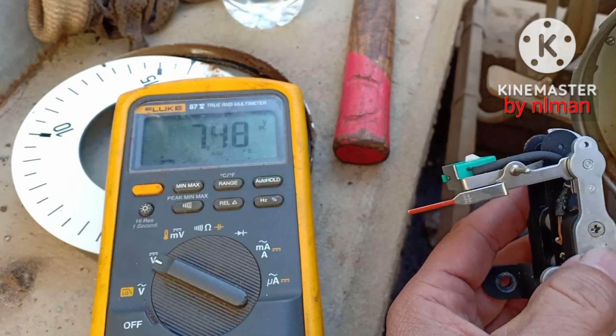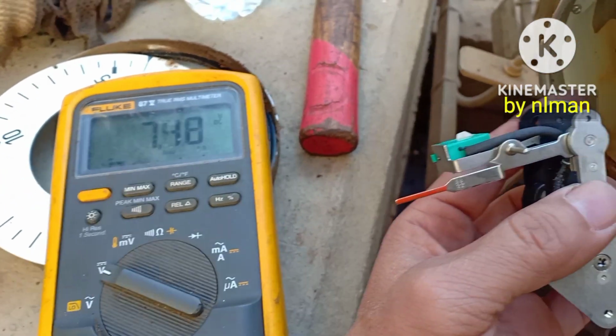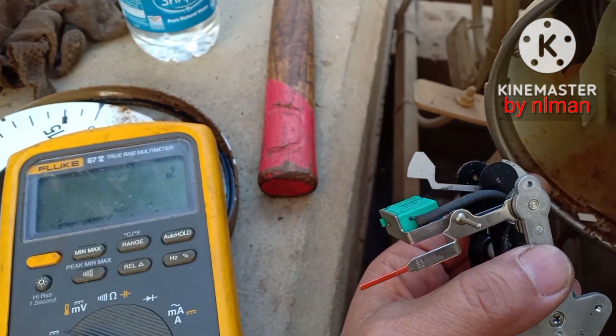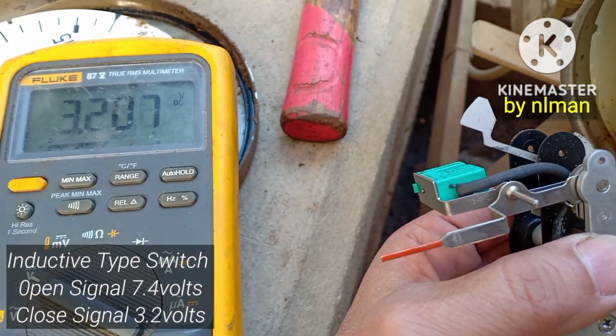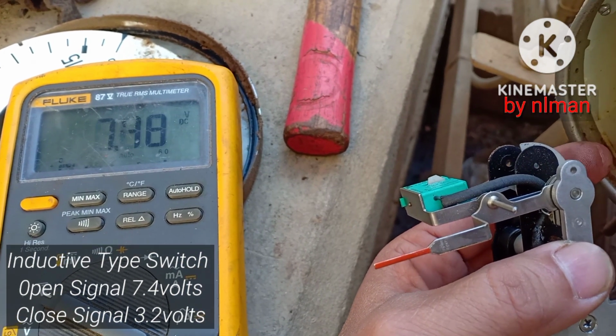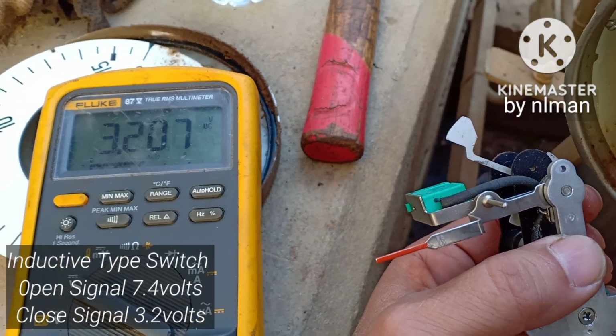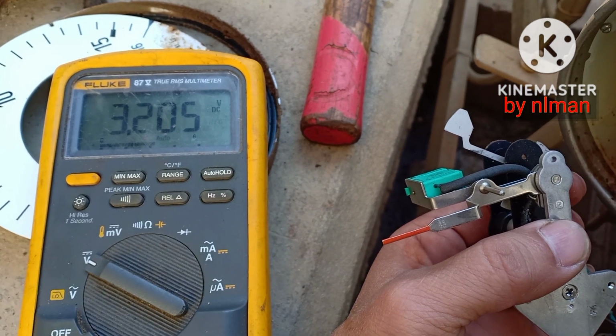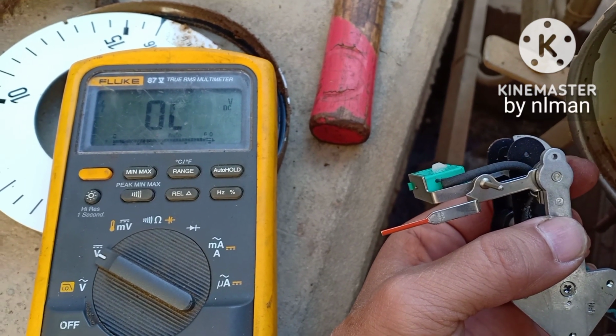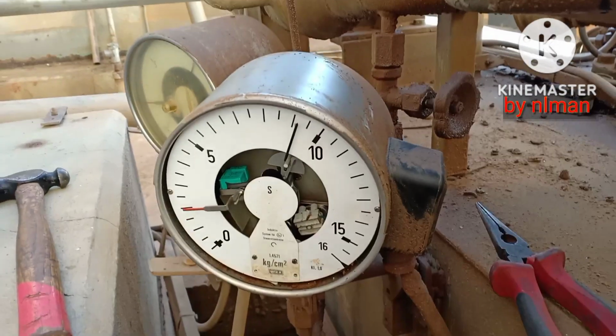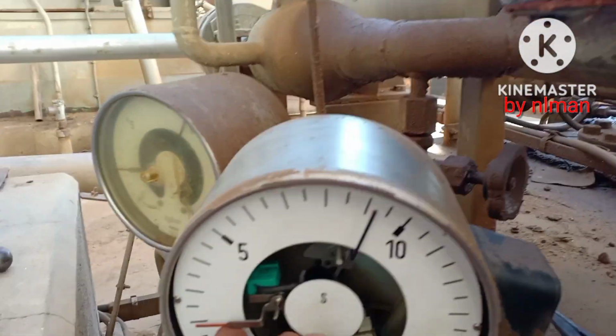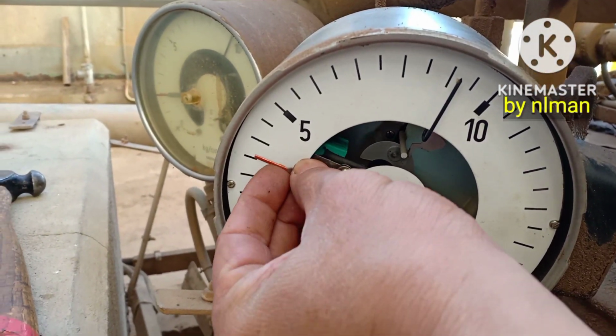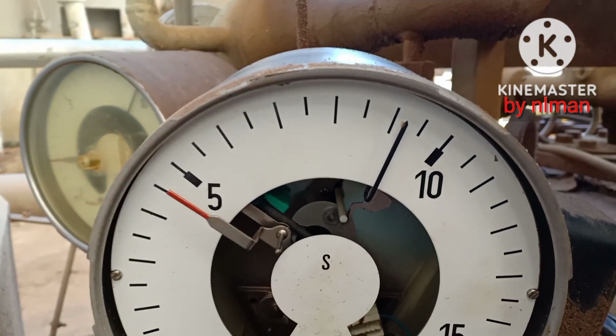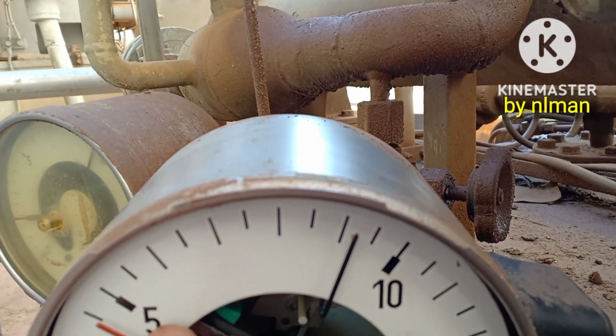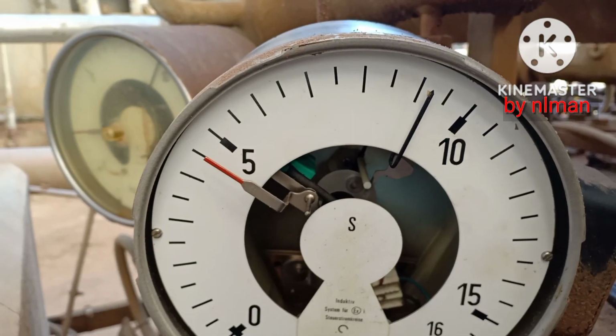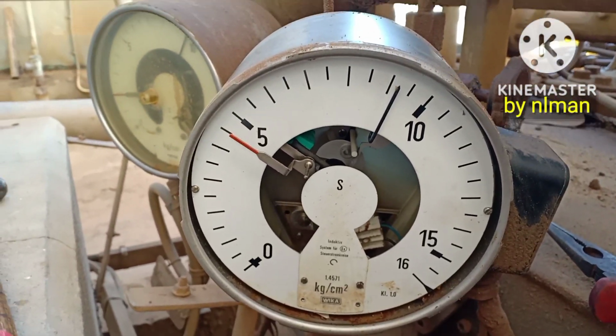But before installing this one, we will check first. For open contact 7.4 and for close contact 3.2. Okay guys, so we found that this one is working. So we are going to install now this new switch. It's already installed, and now we will set it to the original setting at 4.5. Okay, so that's it guys, how to replace a pressure switch.